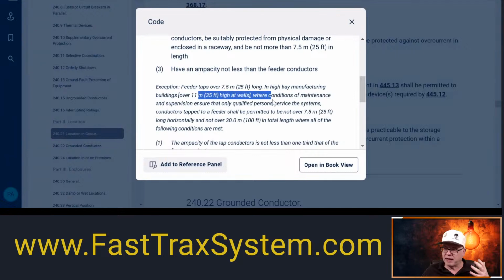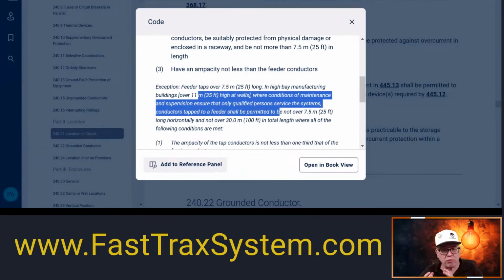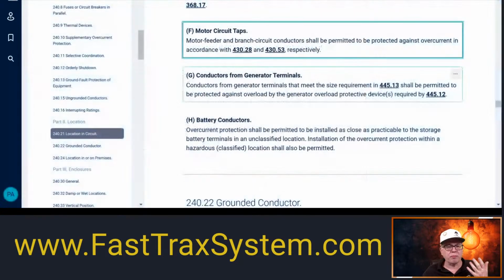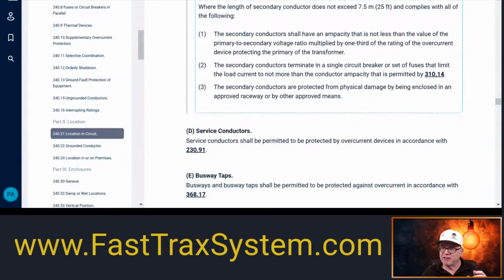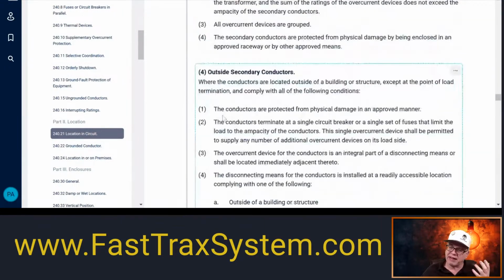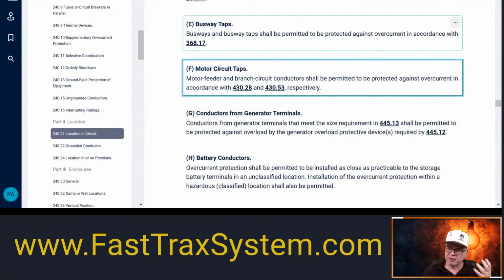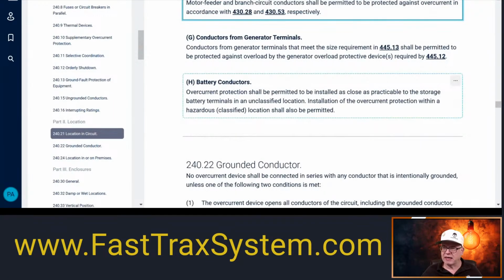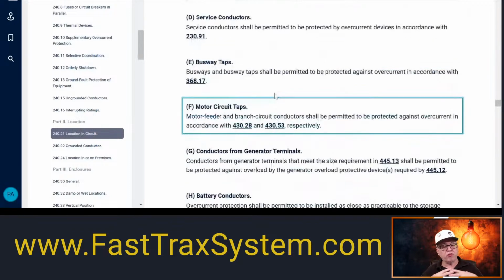Here's that high wall, high bay. So the feeder from motors, they take their own rules in 240.21, and they will modify them to meet that specific condition. So we start out generally with the tap rules, but under the location of the overcurrent, it's not just a secondary rule and it's not just a feeder tap rule. You also have additional allowances down here that you have to be aware of. Keep that in mind when you're applying it. But most of the time, especially if you're exam prepping, it's just going to be the 10-foot rule and 25-foot rule, whether it's feeder taps or secondary conductors, and they basically just follow it item by item. They're pretty straightforward, not too hard to work with.